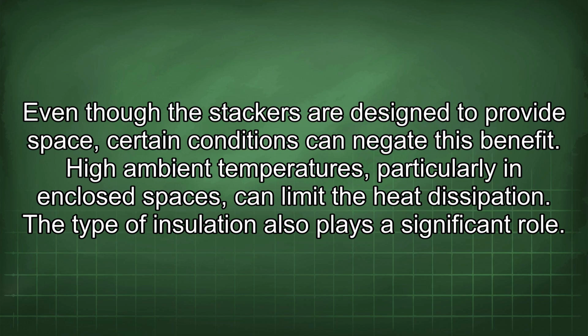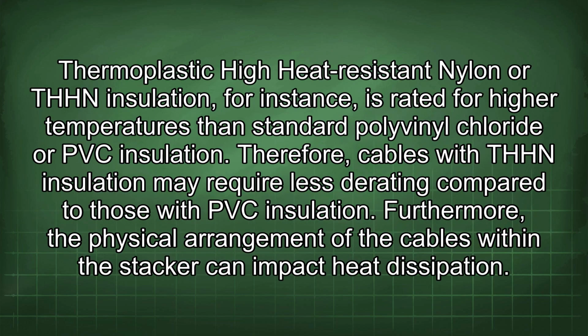High ambient temperatures, particularly in enclosed spaces, can limit the heat dissipation. The type of insulation also plays a significant role. Thermoplastic high heat resistant nylon, or THHN, insulation, for instance, is rated for higher temperatures than standard polyvinyl chloride, or PVC, insulation. Therefore, cables with THHN insulation may require less derating compared to those with PVC insulation. Furthermore, the physical arrangement of the cables within the stacker can impact heat dissipation.